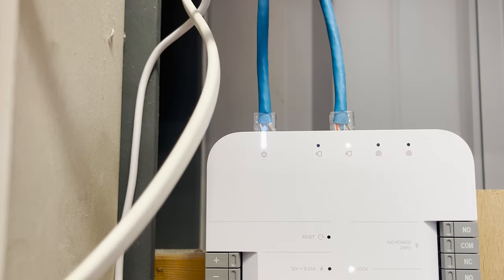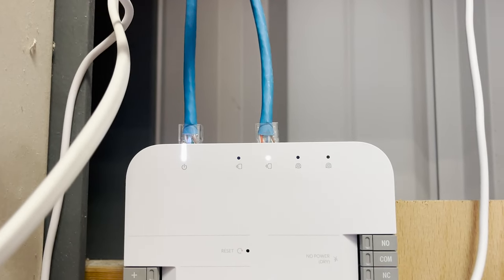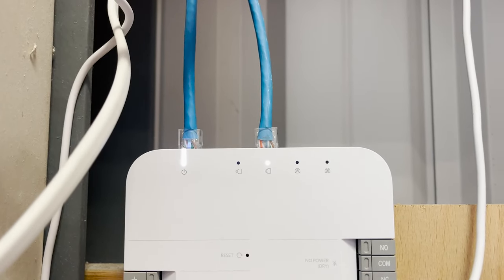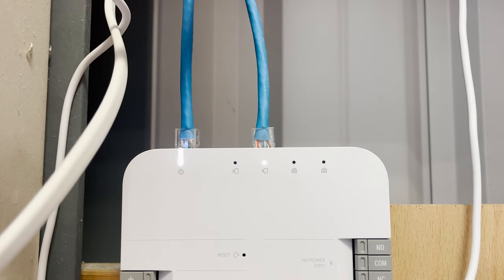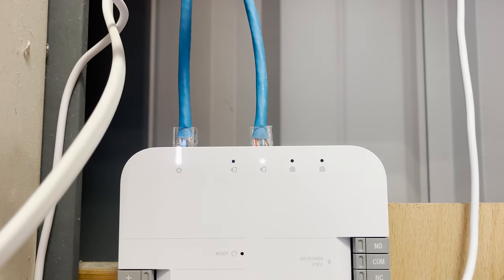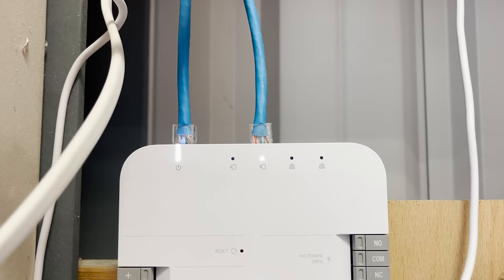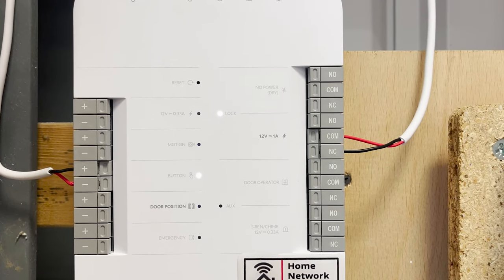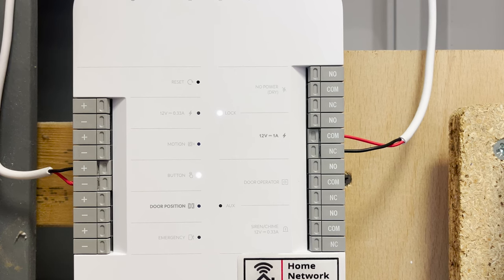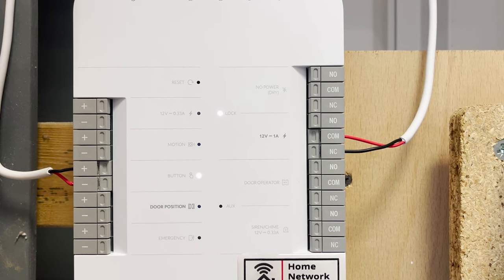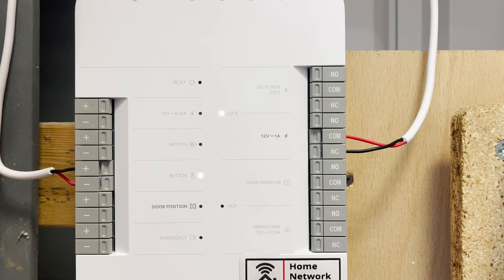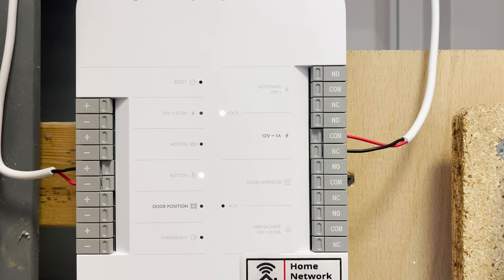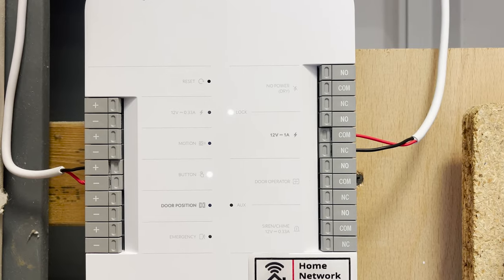Okay so here's the Access hub here. On the left hand side on the top port there you can see my feed coming in from the PoE++ injector. And then on the right hand side we've got another cable which is going to the reader outside. And if you look down here you can see that we've got the two wires going to the 12 volt maglock. This just still is not quite finished yet. We need to tidy up a bit but that's what that's doing. And then on this other side over here we've got the two wires going to the push to release button.